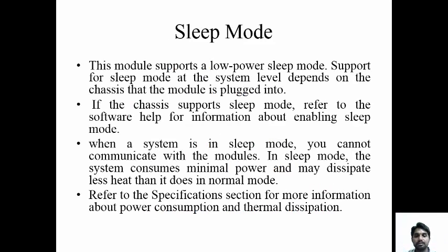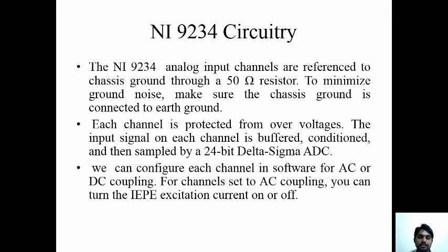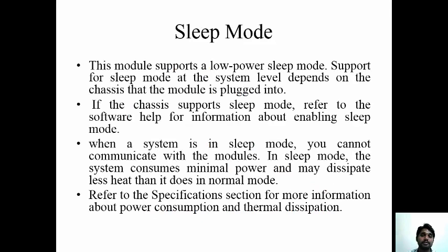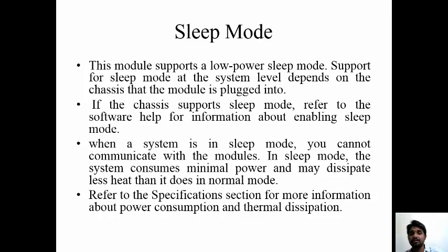Each channel can also be configured in software for AC or DC coupling. For channels set to AC coupling, you can turn on IEPE excitation. IEPE refers to piezoelectric sensors managed via software. A key advantage of the NI9234 is its low power sleep mode. This module supports sleep mode at the system level, depending on the chassis it is plugged into. If the chassis supports sleep mode, refer to the software help for information about enabling it.